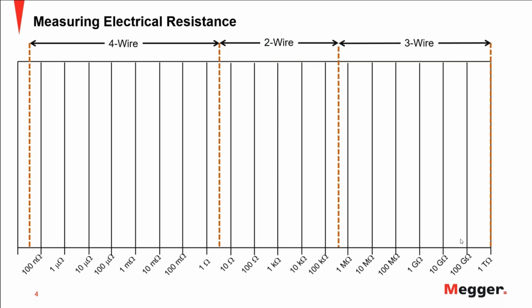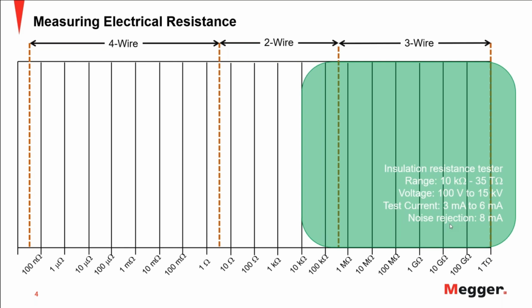So you want to define a method and an instrument to be able to perform the measurement. And as you can see at the top, I'm mentioning 3 methods there. For the high resistance measurements, I have the 3-wire, and that's basically insulation resistance testing, which typically goes from a range of 10 kiloohms to 35 teraohms. The voltage that you apply can go from 100 volts to 15 kilovolts, and it's dependent on the application. The current is not too high. It's in the order of milliamps, and it can go up to 6 milliamps.